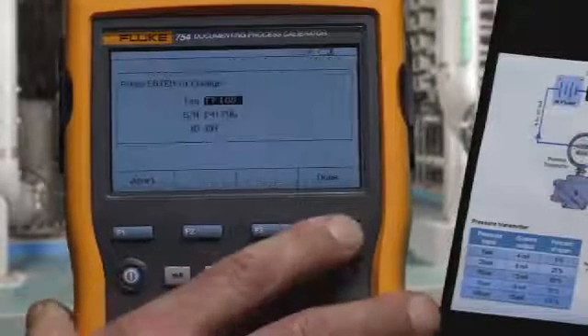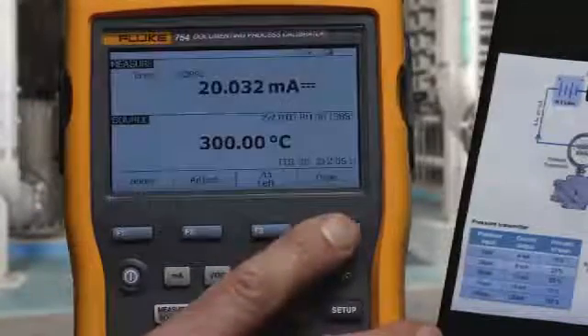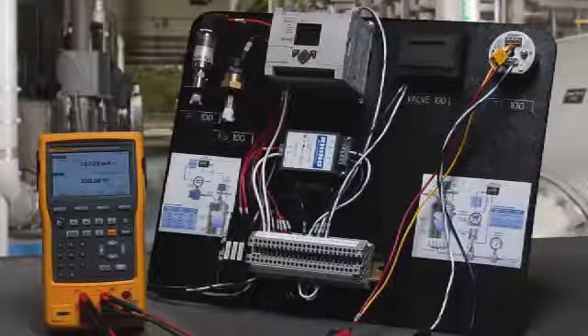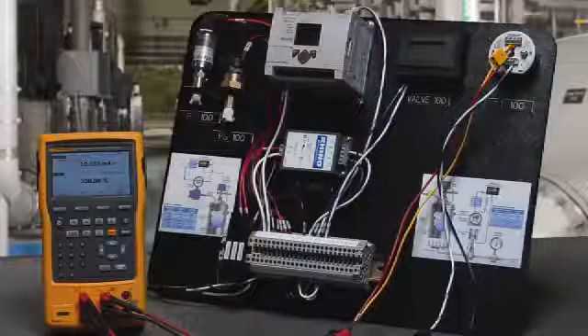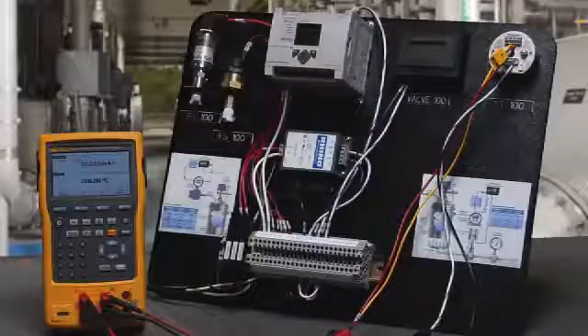It's done, tag serial number and ID of who did the work, and we're done because it passed the test. We have completed documenting the performance of this RTD transmitter using the 754 documenting process calibrator.